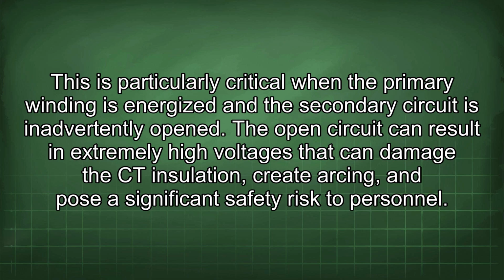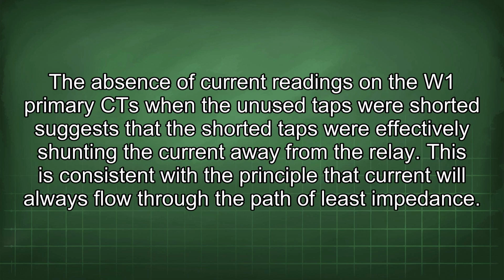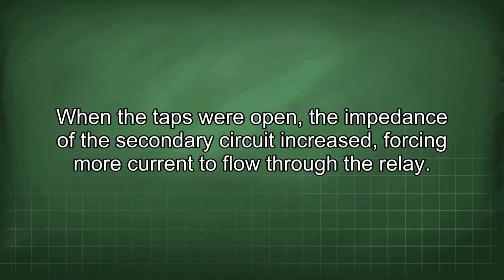The open circuit can result in extremely high voltages that can damage the CT insulation, create arcing, and pose a significant safety risk to personnel. The absence of current readings on the W1 primary CTs when the unused taps were shorted suggests that the shorted taps were effectively shunting the current away from the relay. This is consistent with the principle that current will always flow through the path of least impedance. When the taps were open, the impedance of the secondary circuit increased, forcing more current to flow through the relay.